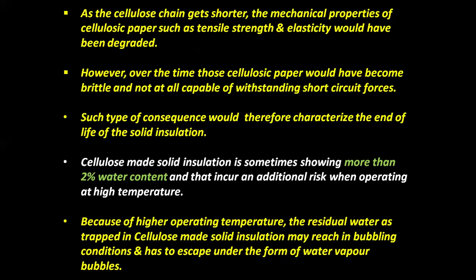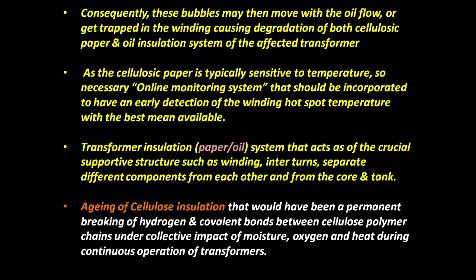Cellulose-made solid insulation sometimes shows more than 2% water content, and that incurs an additional risk when operating at high temperature. Because of higher operating temperature, the residual water trapped in the cellulose solid insulation may reach bubbling conditions and escape in the form of water vapor bubbles. Consequently, these bubbles may move with the oil flow or get trapped in the winding, causing degradation of both the cellulosic paper and the oil insulation system of the affected transformer, as the cellulosic paper is typically sensitive to temperature. So, a necessary online monitoring system should be incorporated for early detection of the winding hotspot temperature by the best means available.